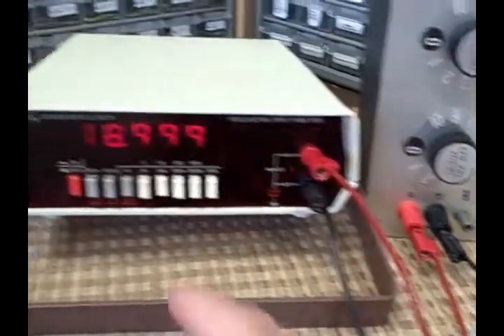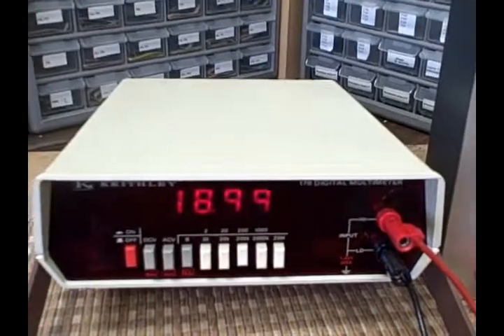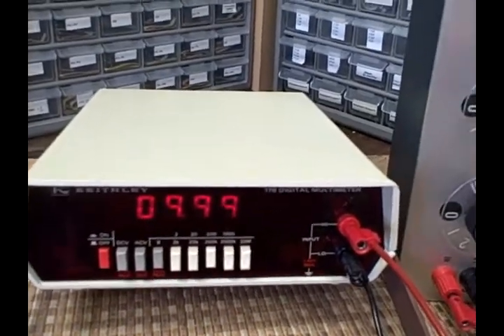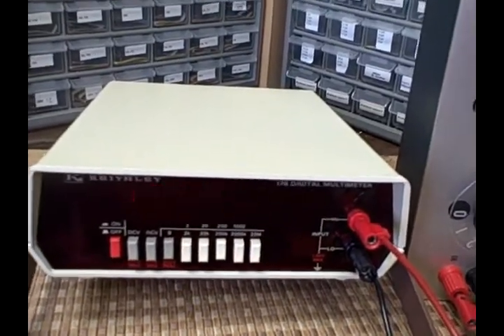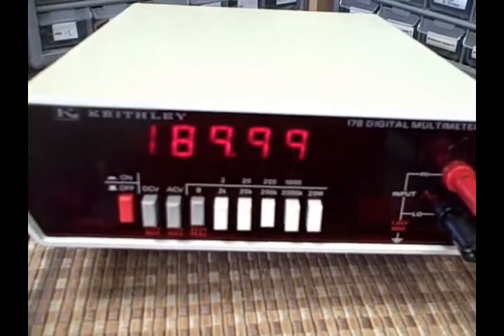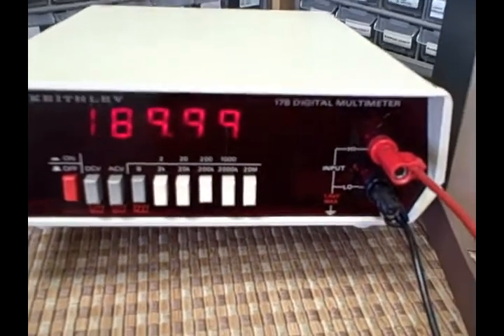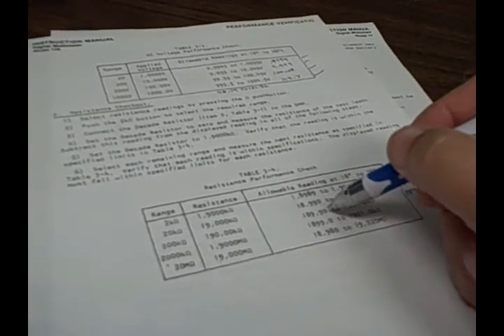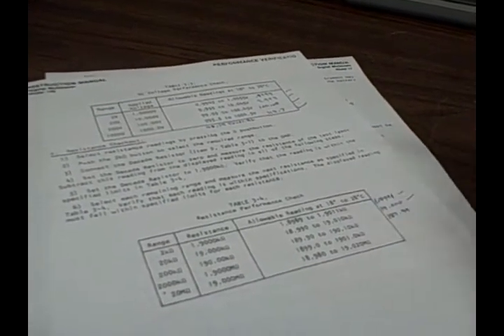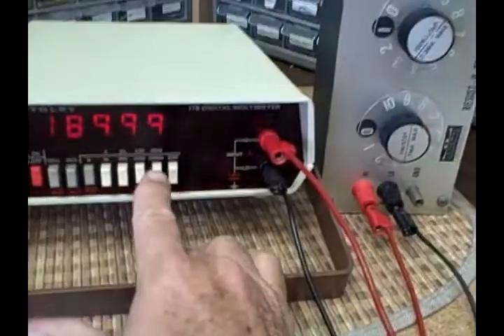Okay, let's move to the 200,000 ohms range, and we want 190,000. Okay, we've got 190,000 ohms on here now, and we're getting a reading of 189.99. We'd be good if we were between 189.90 to 190.10. At 189.99, it's like reading 190. It's really right in the middle. We're good. Let's go to the 2 megohm range.